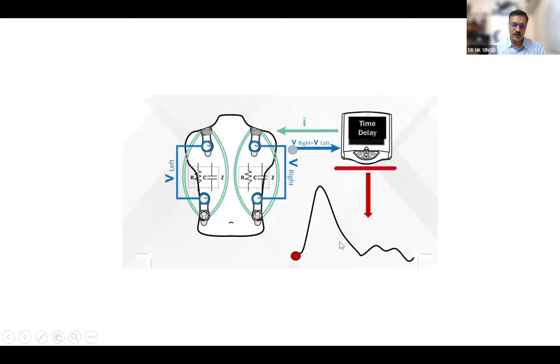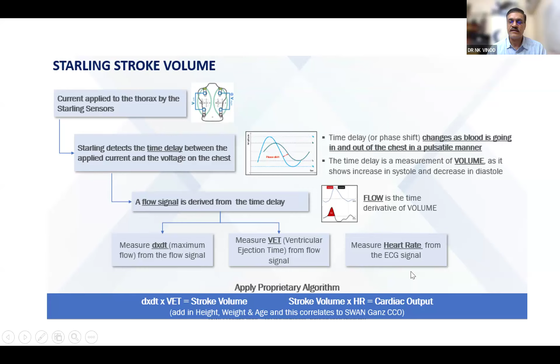So this is the algorithm in which this Starling stroke volume is measured. Current is applied to the thorax by the sensors. The Starling monitor detects the time delay between the applied current and the voltage on the chest. And based on this, a flow signal is derived from the time delay. This measures the maximum dx/dt, that is the maximum flow, and also the ventricular ejection time. And based on a proprietary algorithm, the stroke volume and the cardiac output are determined.